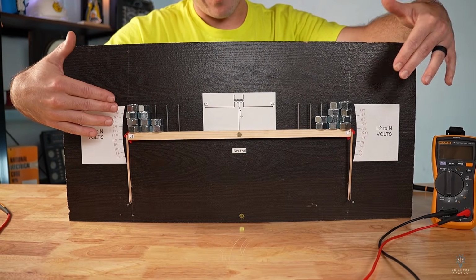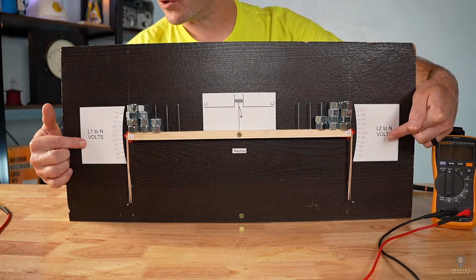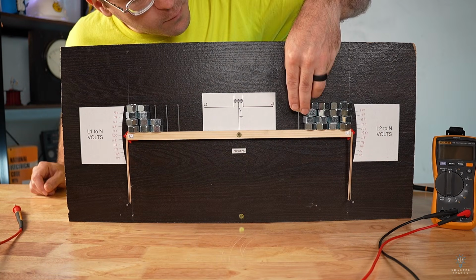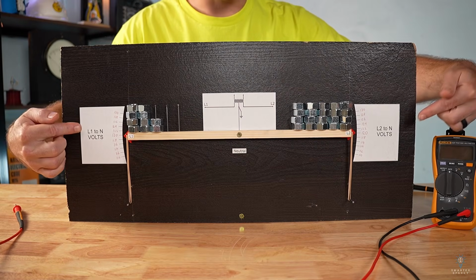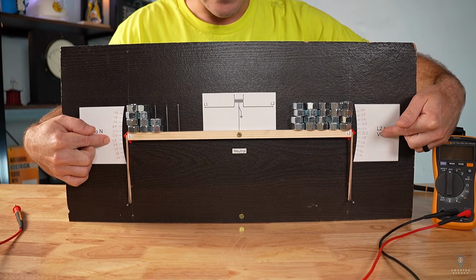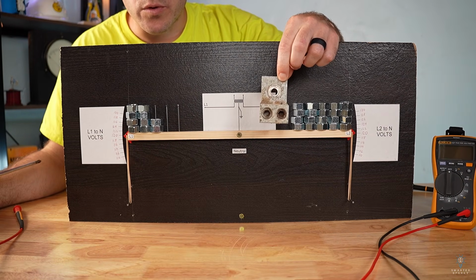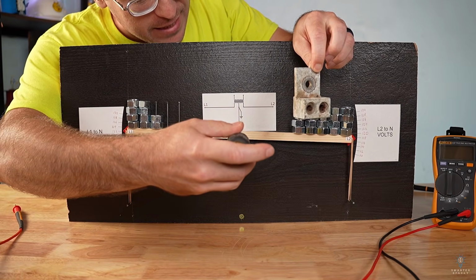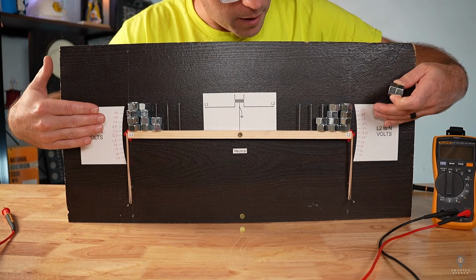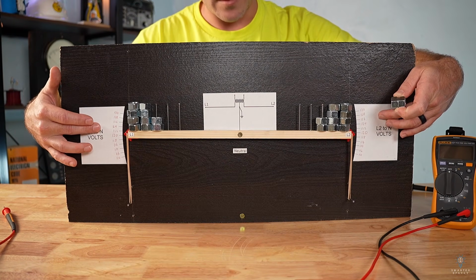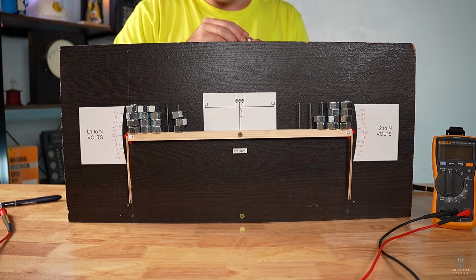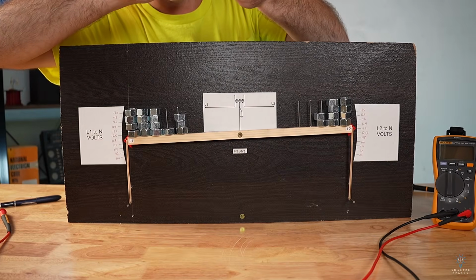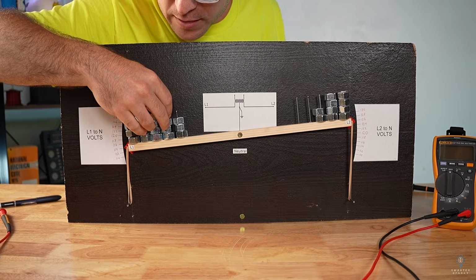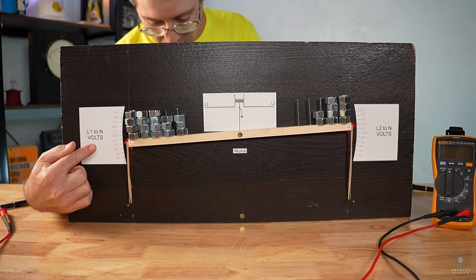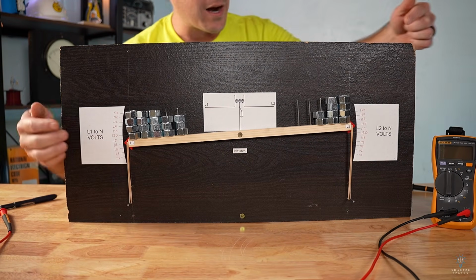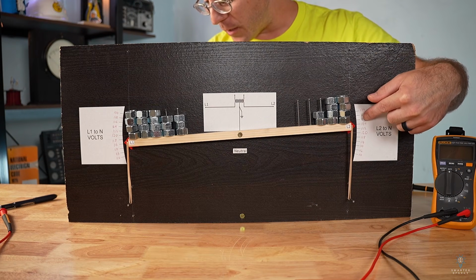If both lines have an equal amount of current on them, the respective line voltages to neutral should stay roughly 120 volts to neutral. And if one line has more current on it than the other, we should still see a relative voltage to neutral on each line of approximately 120 volts. But a loose or corroded neutral connection is going to act like this center pivot is loose. Now, if both lines to neutral have an equal amount of current on them, notice they balance out to 120 volts. But if a large load is added from one of the lines to neutral, such as a sump pump kicking in, or a dehumidifier turning on, or an air conditioner kicking in, notice the extra weight on that line actually causes the voltage on that heavier line to drop, whereas the line with the lighter load on it is actually going to rise in voltage.